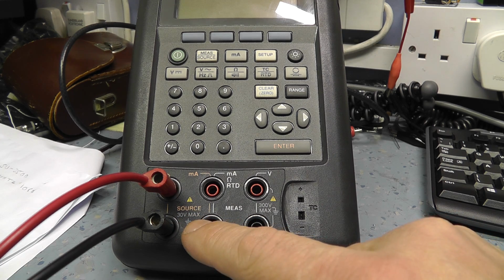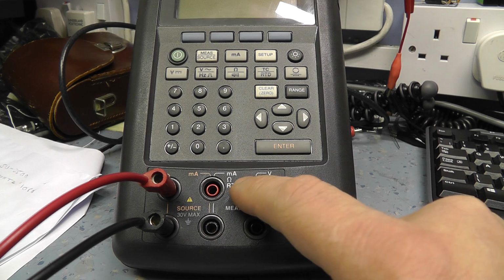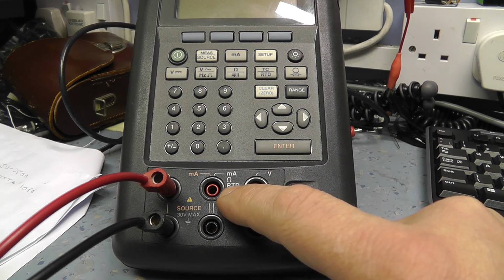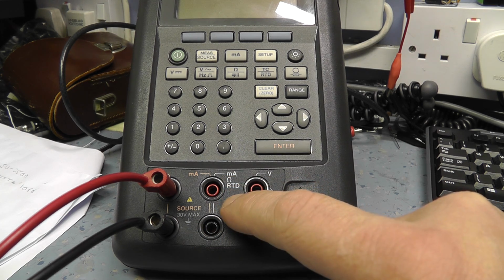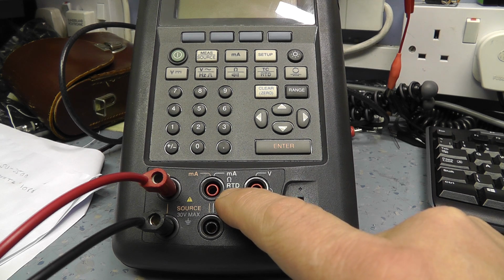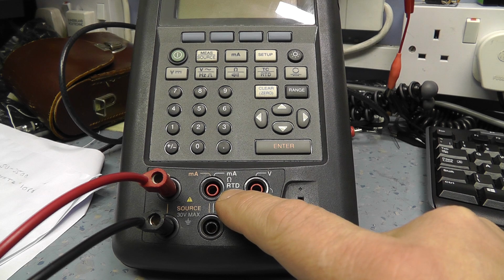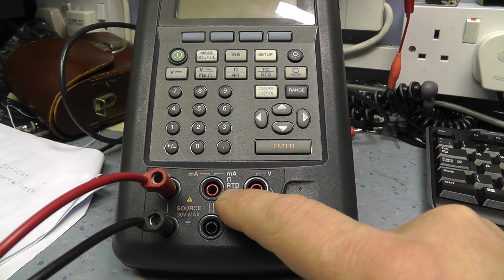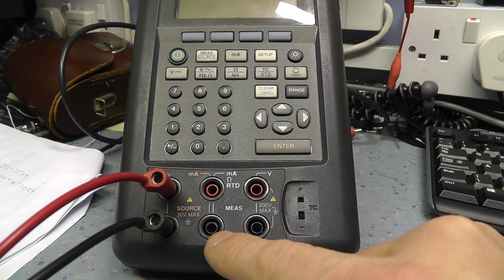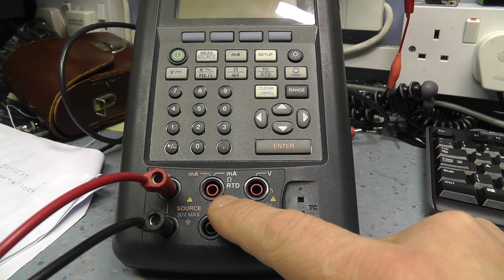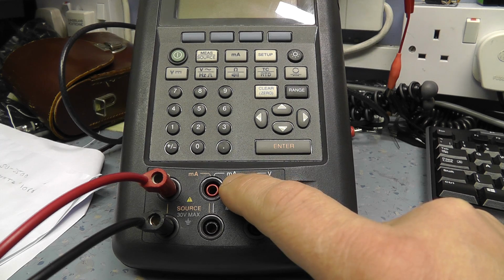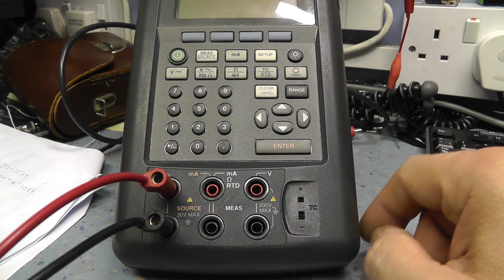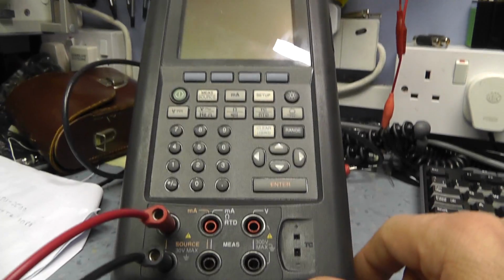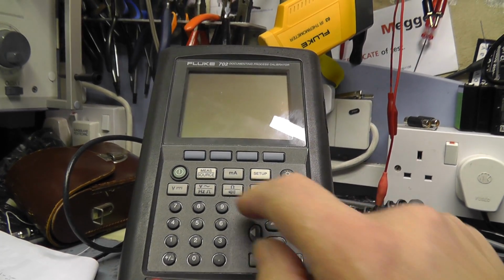You wouldn't want to do that, so you have to be a bit careful when you use this. And our current measuring, resistance measuring, and thermocouple measuring - if we're actually measuring the resistance from our PT100 thermometer for example, we use these 4 wires here, the 4-wire sense section, and likewise milliamps and volts are registered here. So let's just power it up quickly and show you roughly what it does.